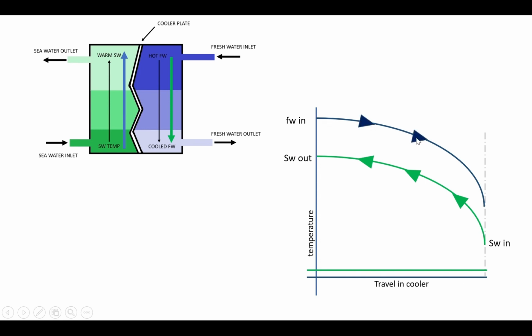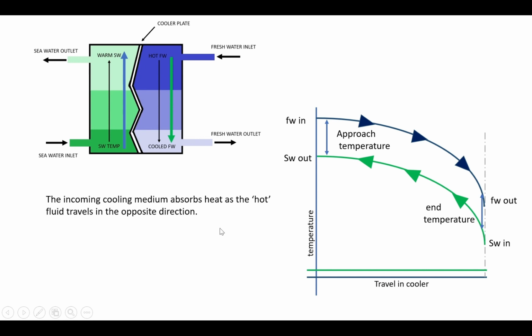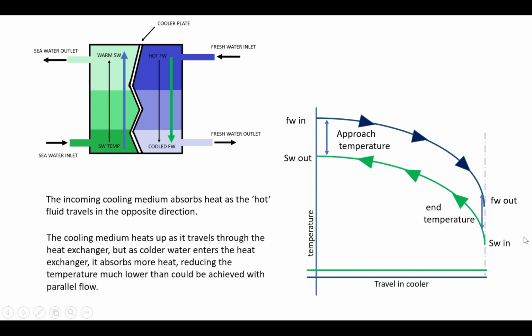Fresh water cooling starts at warm seawater as it passes through the seawater cold region for optimum heat transfer. Fresh water is cooled below warm seawater temperature. The incoming cooling medium, seawater, absorbs heat from the hot fluid, fresh water, as it travels in the opposite direction. The seawater heats up as it travels through the cooler, but as colder water enters the cooler, it absorbs more heat, reducing the temperature of fresh water to much lower than could be achieved with parallel flow.